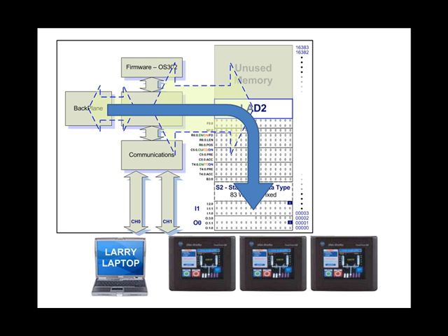That is 920 words, one at a time over the backplane into the PLC's data file number 1, and then another 920 words transferred out of the PLC's data file 0 to the individual slots that have output cards, one word at a time. Once the processor has a fresh snapshot of the input states, it begins accessing the logic one rung at a time.